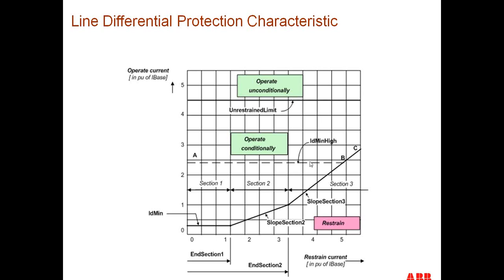ID min high is a value that's used on some relays, and this is used if we have an open circuit CT problem, so that we actually shift the level of the operating of the relay to compensate for that open circuit CT, rather than shutting the relay down. And we'll go on further.